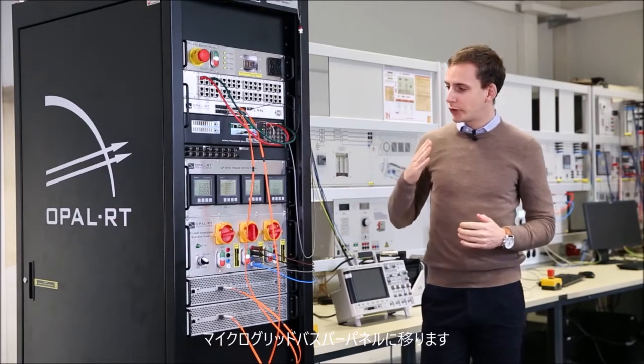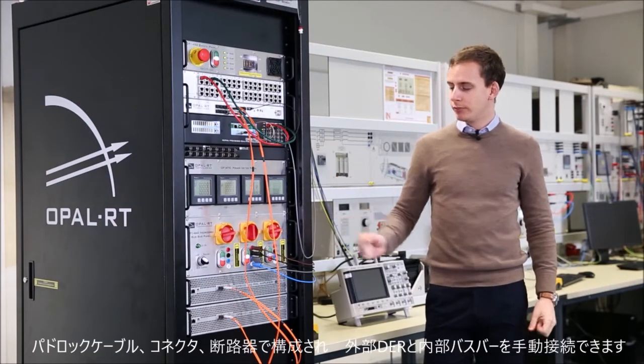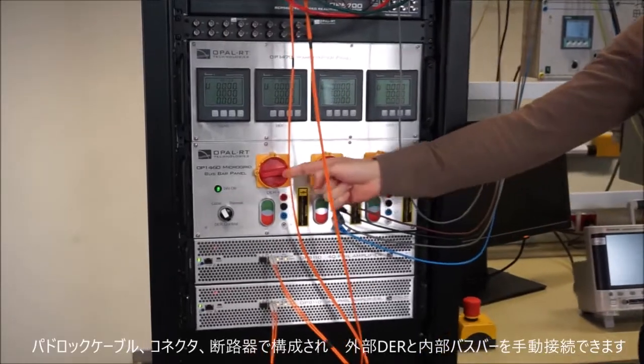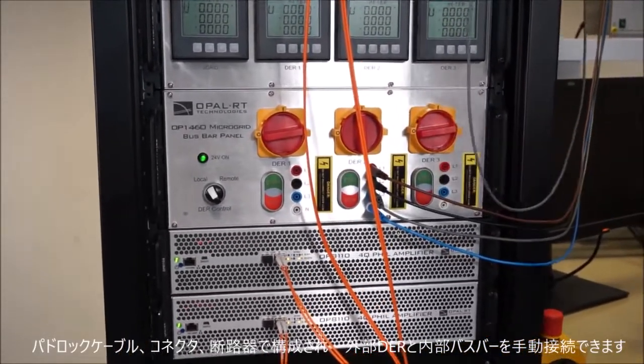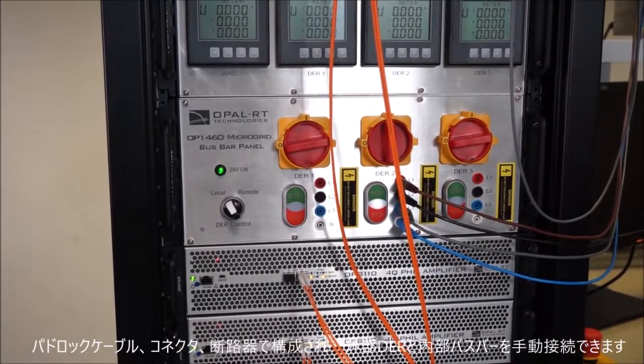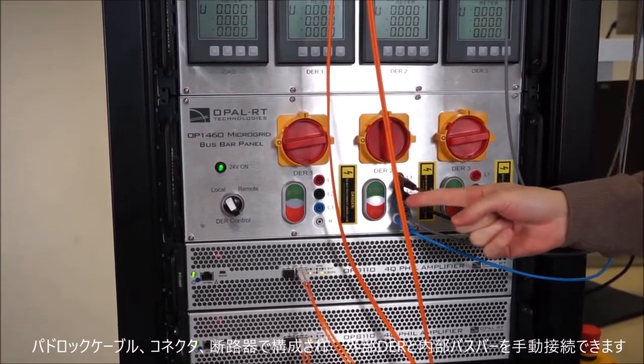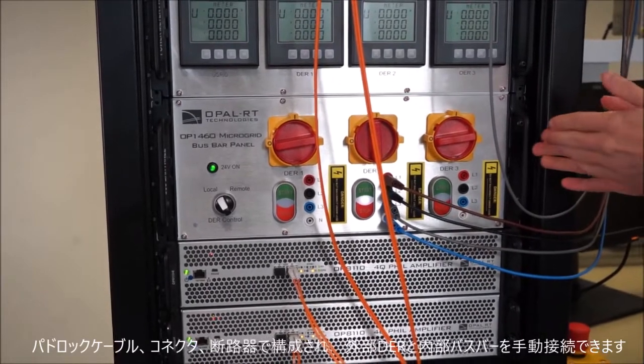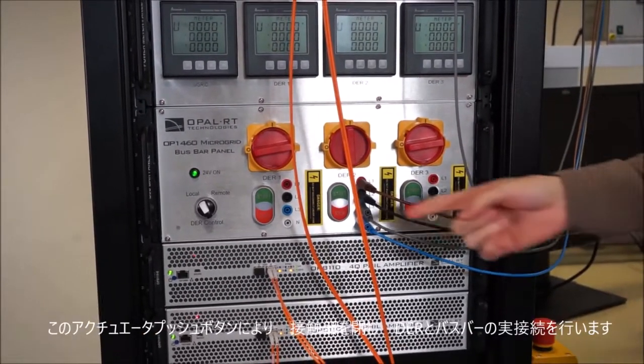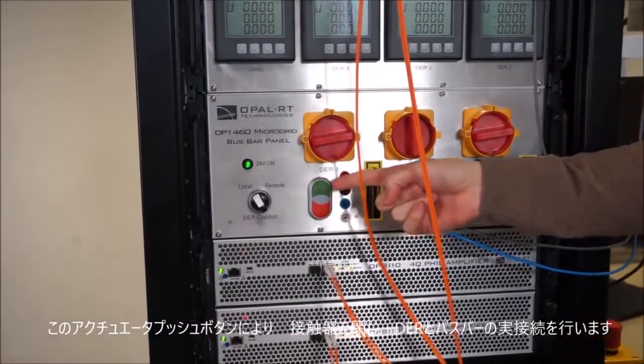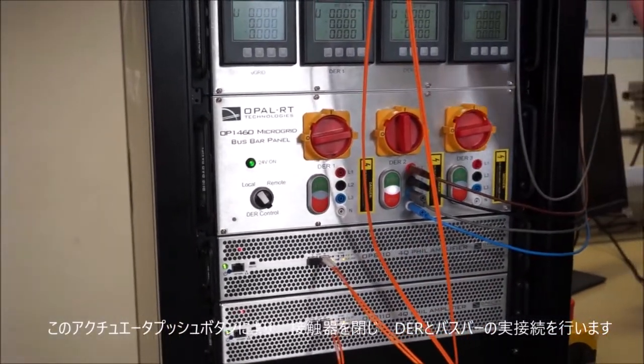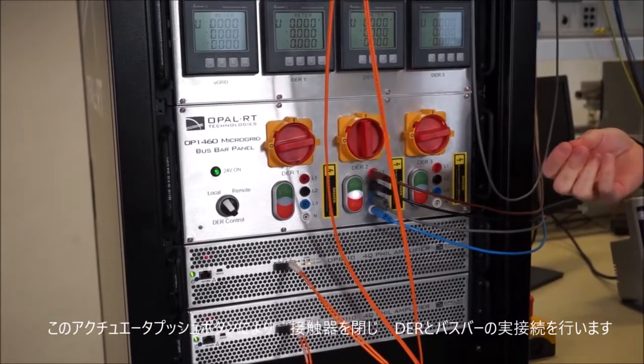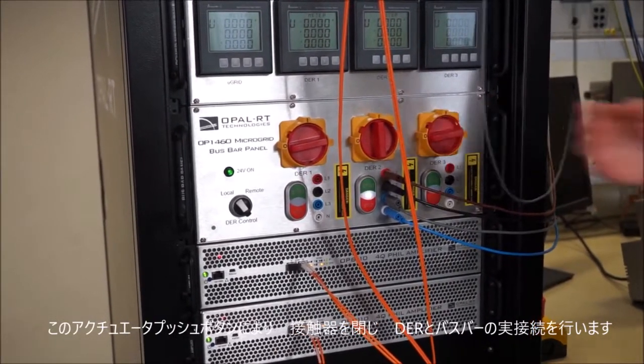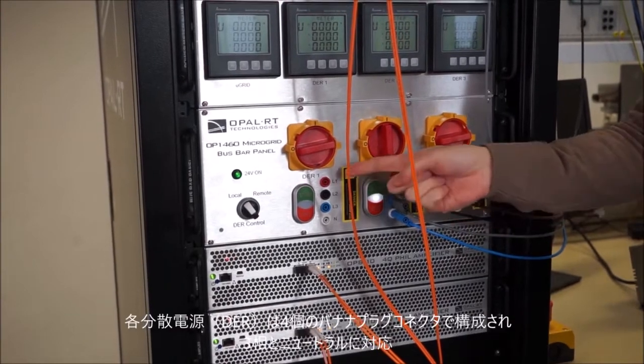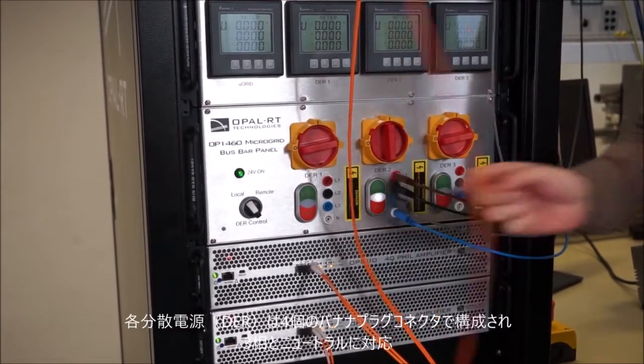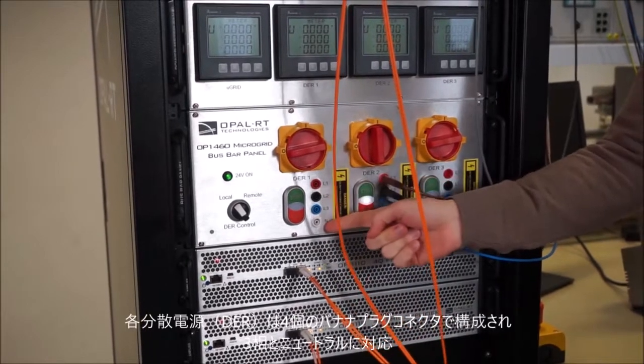We can switch now to this microgrid busbar panel. It is composed by padlockable connector disconnectors, which allows to manually connect external DER to the internal bus bar. This actuator push button allows the contactor to close to have the physical connection of this DER to the bus bar. Each DER is composed by 4 banana plug connectors for the 3 phases and the neutral.